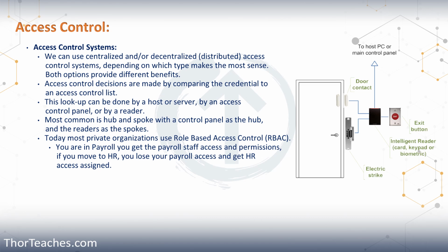So the black thing you can see here in the middle, that's the one I swipe my key card to, or I punch in my PIN or my fingerprint or whatever. That is the interface I interact with. That is then connected to the actual lock. It is connected to a door contact, and an emergency exit button that would normally be on the other side of the wall. In most places, we would have the access control going into the room, not leaving the room. We want a secure exit. And then the actual arrow up goes to the main panel, the actual access control system.